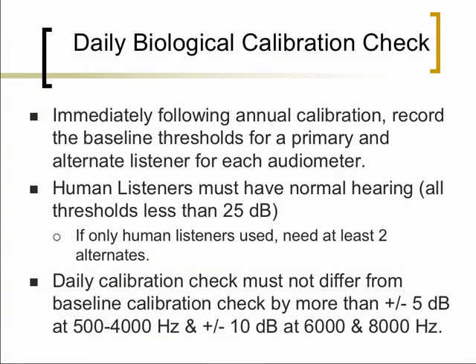So immediately following the annual calibration, you'll record those baseline thresholds from this primary listener, and sometimes, if you have the luxury, you might have a second listener also, just in case the primary listener is not available on any given day. You'll have a backup. So we would want to try to get a person with normal hearing thresholds, and that would be the baseline. And when you bring this person back for your daily calibration, you want to make sure that his or her thresholds do not change dramatically. So it's not more than plus or minus 5 dB up to 4 kilohertz, and plus or minus 10 dB at 6 and 8 kilohertz.